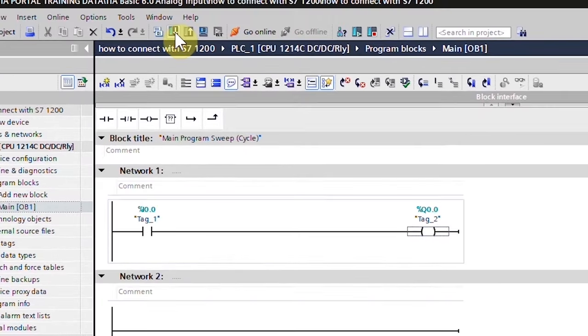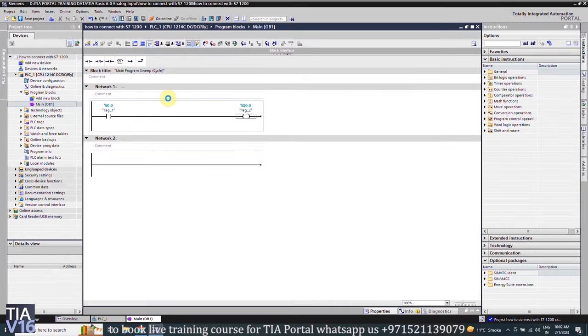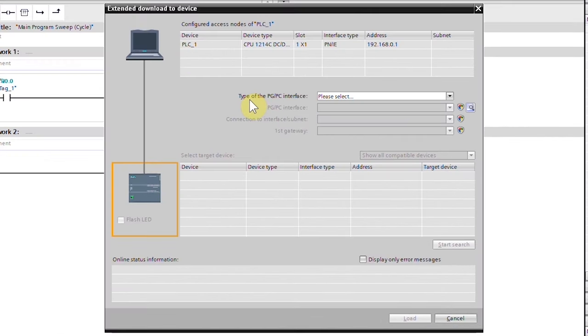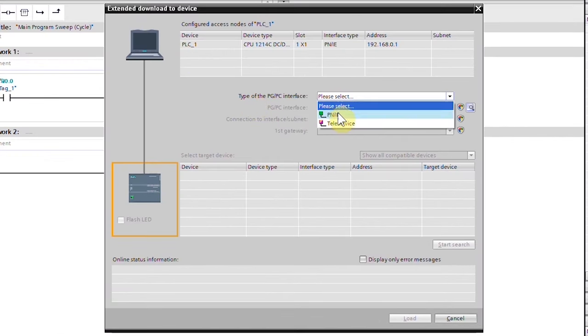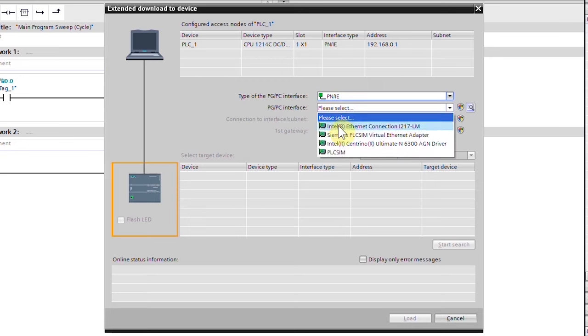Next, we will download this program into the PLC by clicking on the download button. Here we have to select the interface to connect with the PLC. From the drop-down menu, we will select the PROFINET channel. Next, we will select the ethernet card of the PC and click on the search button.